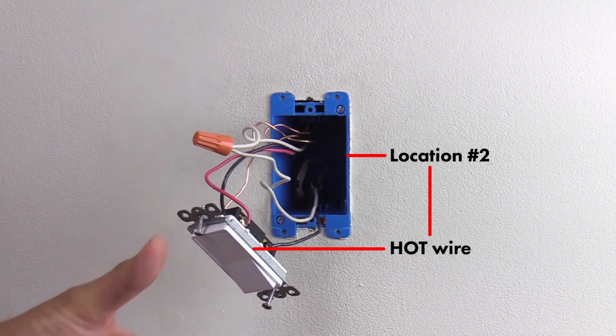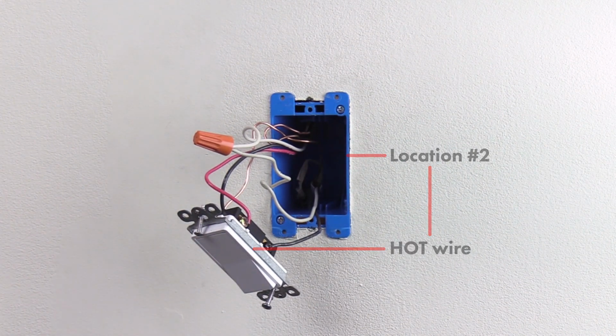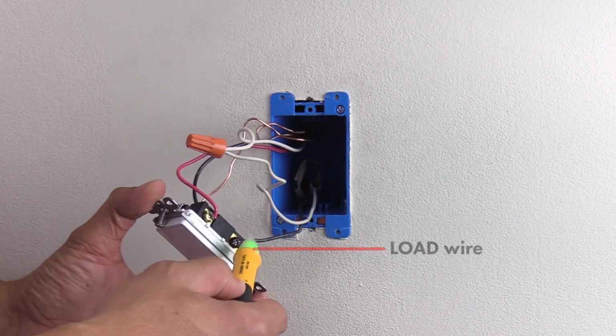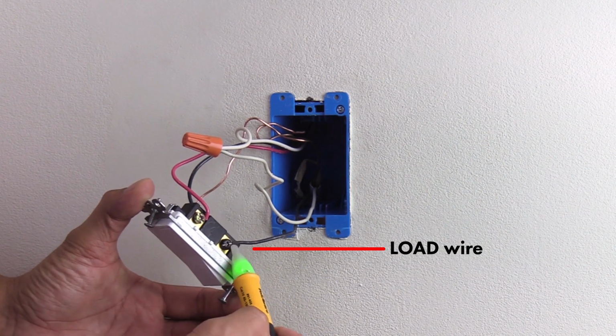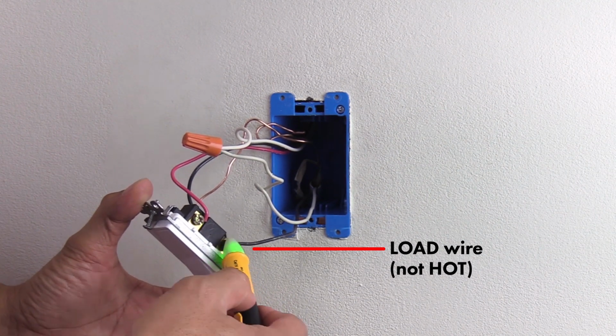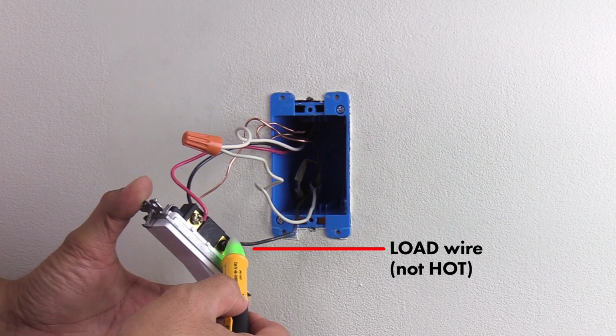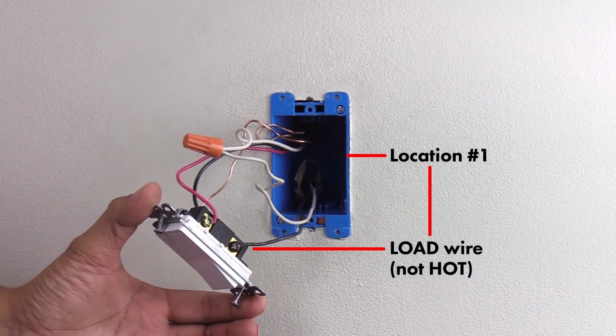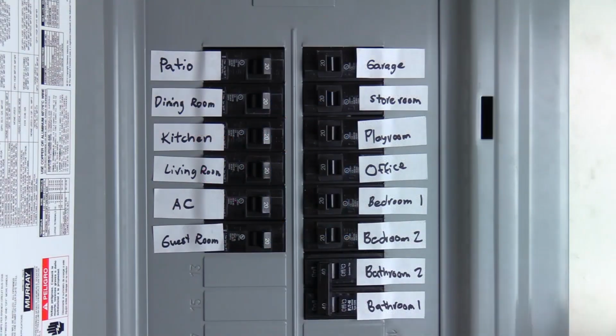We will call this location number 2 for our reference. The same black terminal at the second location will have the load wire. Test this terminal to confirm that it is not hot. This will be location number 1. Turn the power off from the electrical panel.